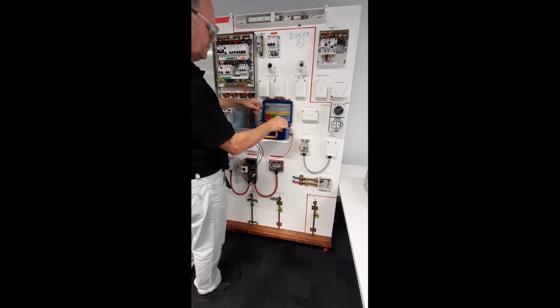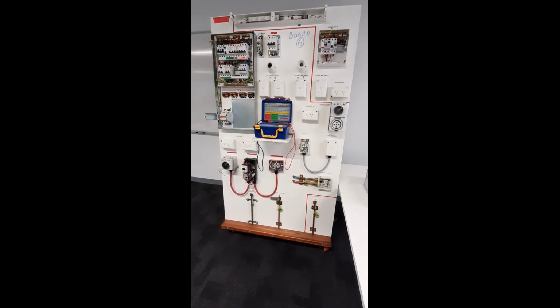Infinity. Any results less than 1 megaohm identifies a faulty circuit. After repairing the fault, you should retest the whole installation to confirm no short circuits still exist. You are now ready to conduct polarity testing of the electrical installation.